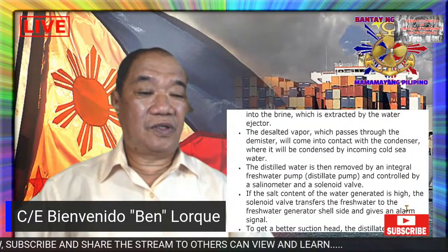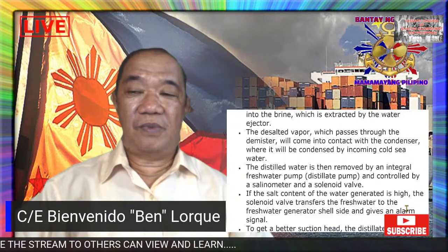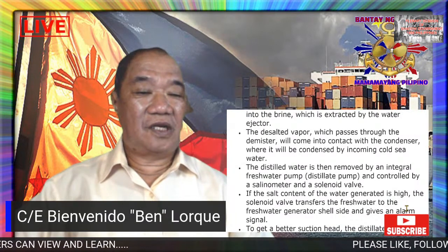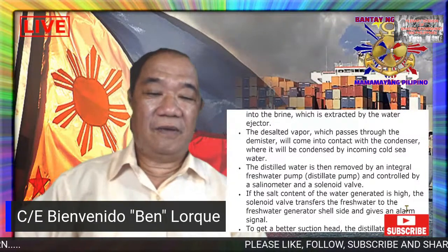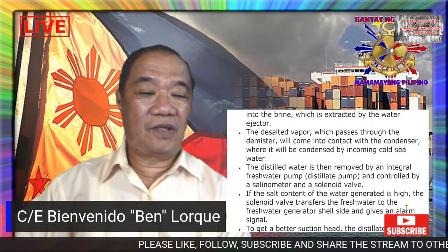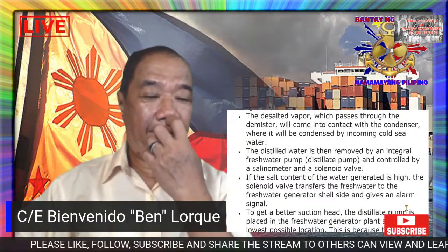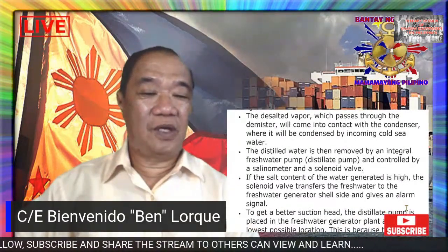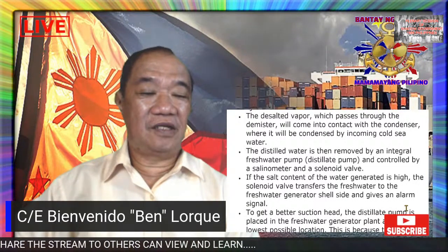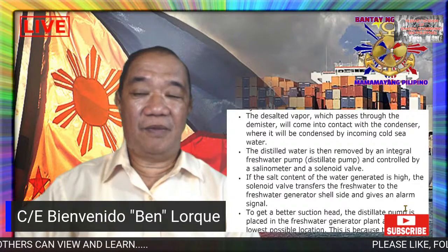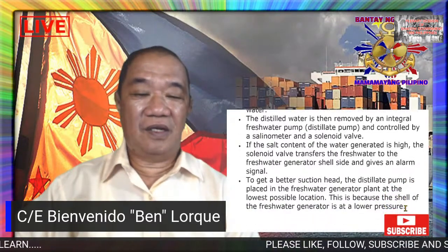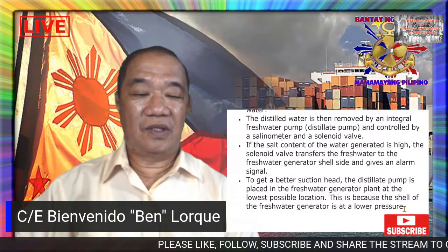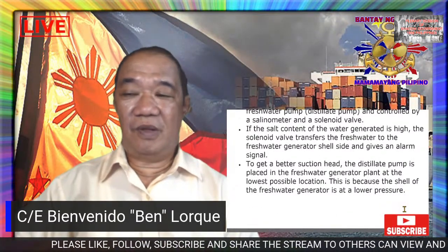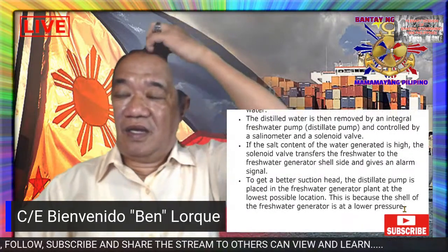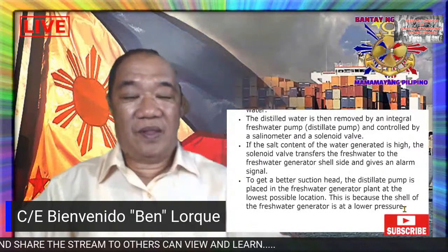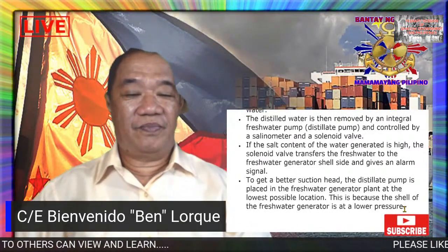The distilled water is then removed by an integral freshwater pump or distillate pump and controlled by the salinometer and the solenoid valve. If the salt content of the water generated is high, the solenoid valve diverts the water back to the freshwater generator shell side and gives an alarm signal. Once it alarms, the engineer will go there and check what causes the alarm. If the vacuum is low, you have to increase the vacuum.